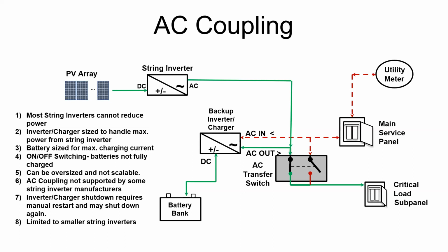With AC coupling, you're going through a double conversion process, which in and of itself is inefficient if you don't need it. Again, what's happening here is you have your PV array feeding your string inverter. That's inverting DC to AC. And what you're actually doing is you're backfeeding the AC output of your battery-based backup inverter charger to fool it into thinking that the grid is present. And so the string inverter is allowed to push energy through the AC output of the backup inverter charger and backfeed this AC to DC rectification stage to charge the battery bank, albeit fairly unregulated.